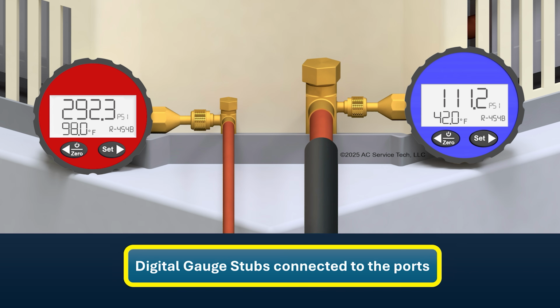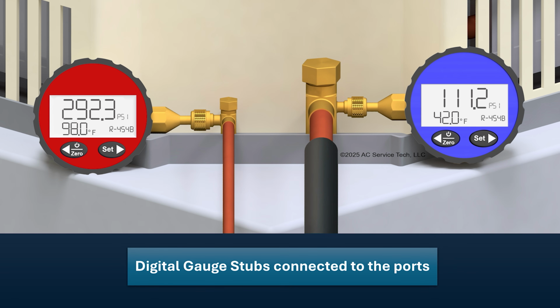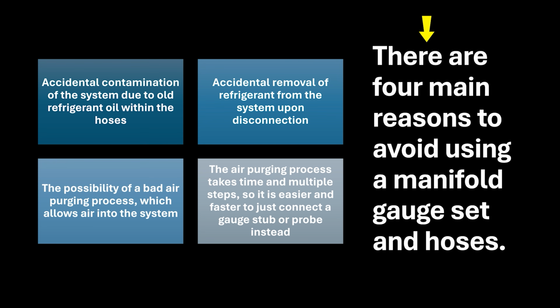Gauge stubs, see figure 4-42, can be connected to the ports instead of a manifold gauge set with hoses in order to avoid the use of hoses. There are 4 main reasons to avoid using a manifold gauge set and hoses. Accidental contamination of the system due to old refrigerant oil within the hoses. Accidental removal of refrigerant from the system upon disconnection. The possibility of a bad air purging process which allows air into the system.